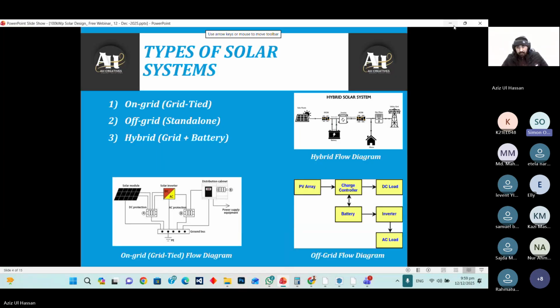When you have a grid-connected system using a grid-following inverter, we have grid following and grid forming. The grid-following inverter requires a reference voltage and frequency from the grid. Also, it safeguards personnel working on the grid, because the grid could be off due to maintenance or faults. If the inverter keeps sending power to the grid, it is going to be dangerous and harm whoever is on the line for maintenance. So the system is designed to go off whenever the voltage or frequency from the grid is off. I think by IEC standard it is within two seconds. When it notices that there is no reference voltage from the grid, it trips off.